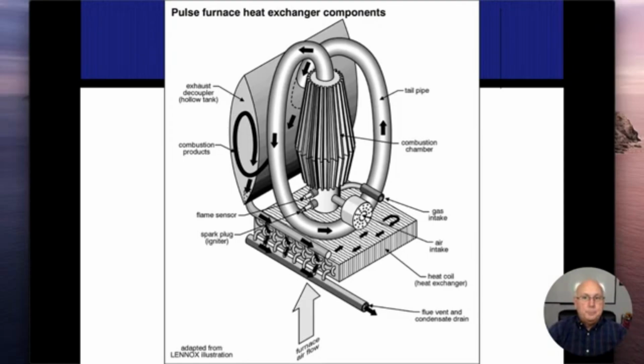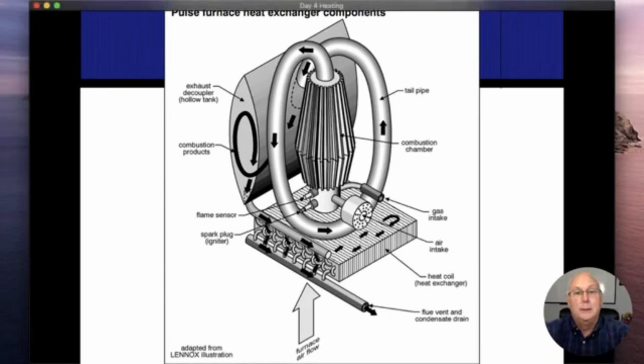This is where you start seeing decouplers on ductwork, because these would vibrate when they would run, just like you would feel the vibrations of a lawnmower running. These would do that, and they would rattle the entire ductwork. So they would have to put their plenum up, and then they would put about an inch or 6 inches of rubber ductwork or some sort on there. And so as that thing would vibrate, it wouldn't vibrate the rest of the ductwork in the house. And they would have to do the same thing with the return ductwork as well. That actually turned out to be a standard practice for a long time, and people were putting that in on many furnaces. But it's kind of gone by the wayside, and we don't see it anymore. And so that's called a Lennox Pulse.